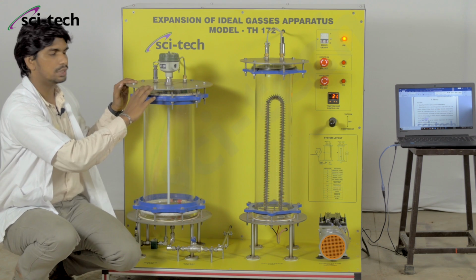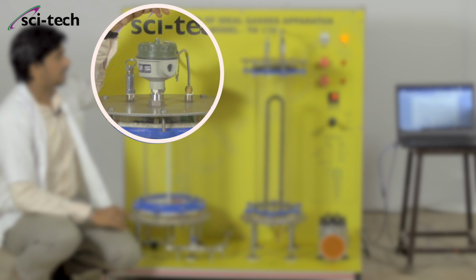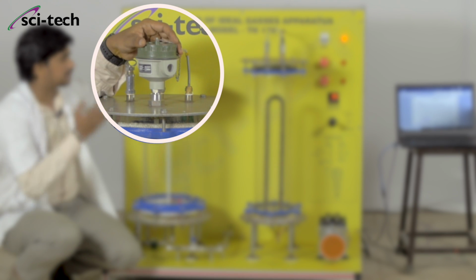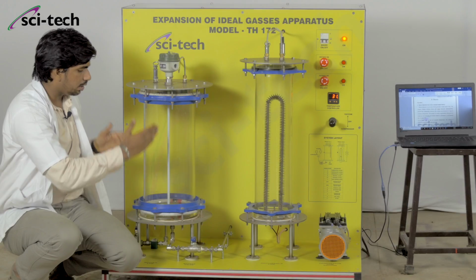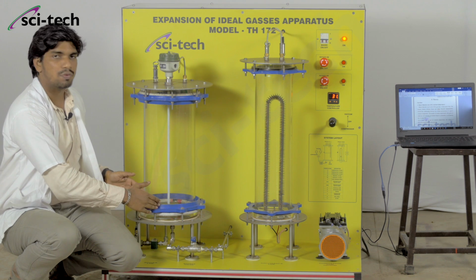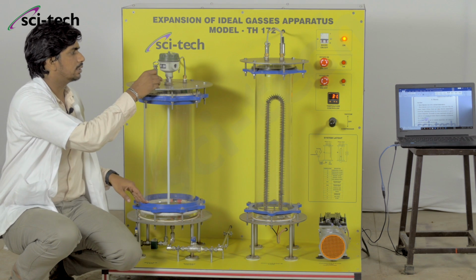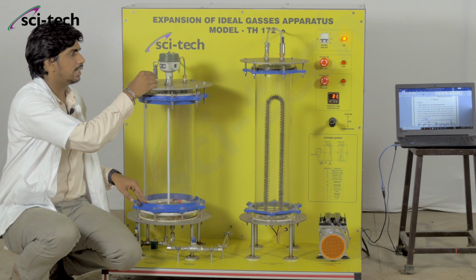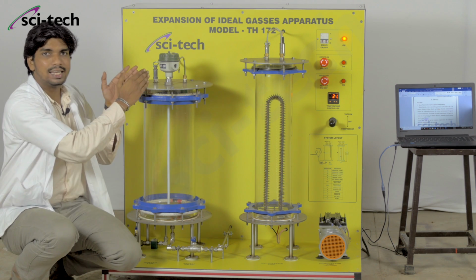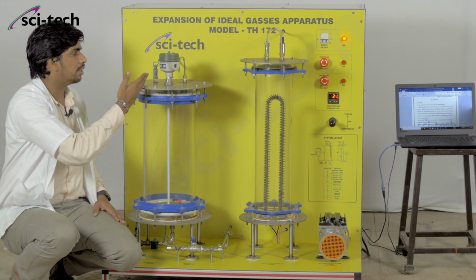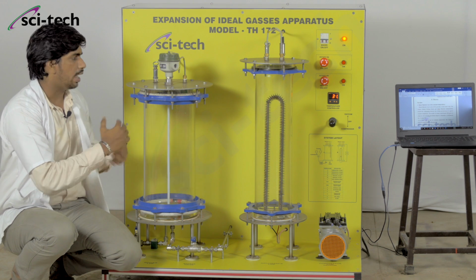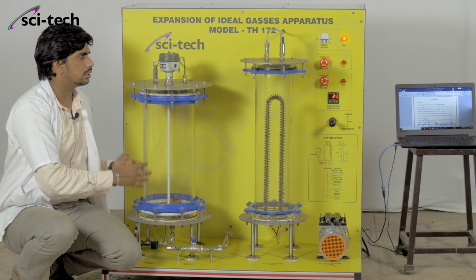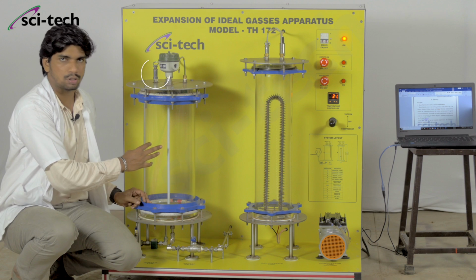This top flange consists of one level sensor which is of capacitance type, and it has a probe of maximum height 540 mm. This capacitance level sensor model is SC701 and the range is 4 to 20 milliampere for the electric signal, and for the calculation part the range is around 0 to 540 mm approximately.